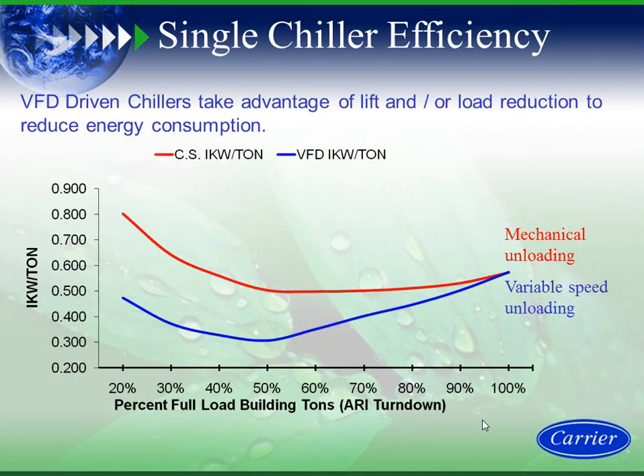Let's look at a single chiller plant. We're going to analyze both a constant speed machine and a variable speed machine. At the 100% load point, the two are virtually the same, right? The kW per ton with a variable speed drive versus a non-variable speed drive are virtually the same. Sometimes the variable speed drive may be less efficient, sometimes more efficient, based on where it's at on the compressor map on the machine itself.